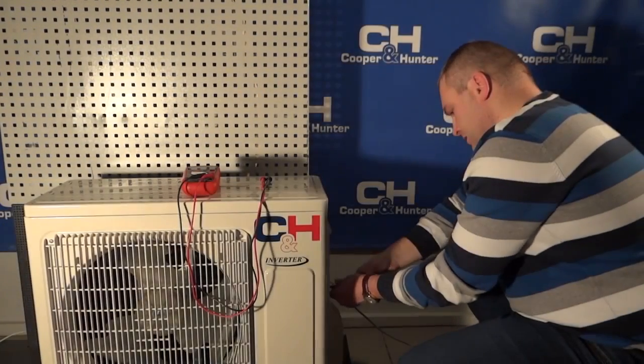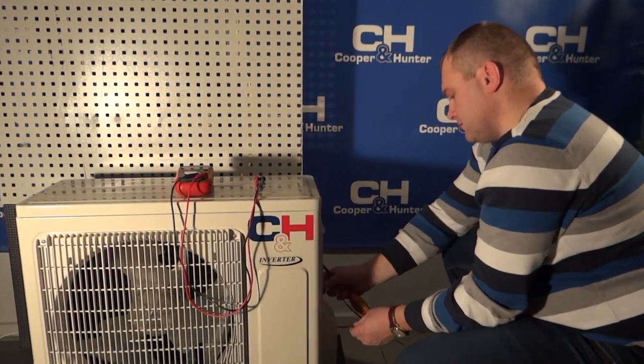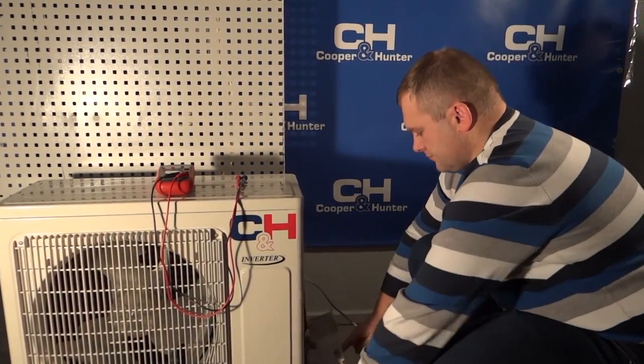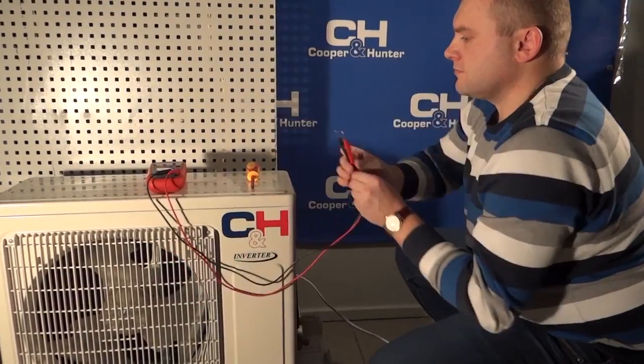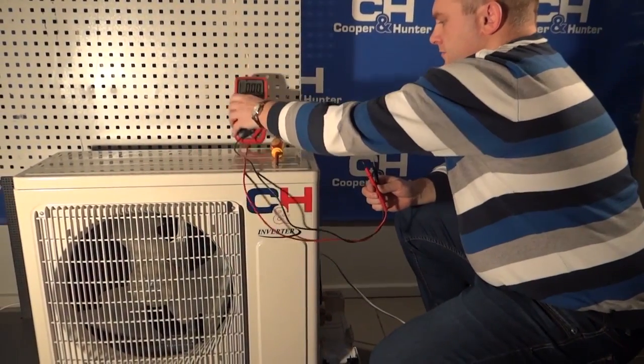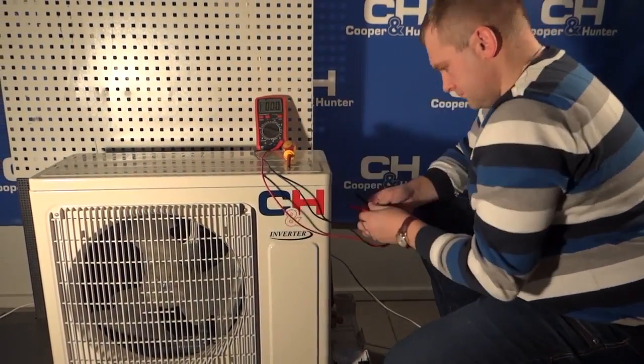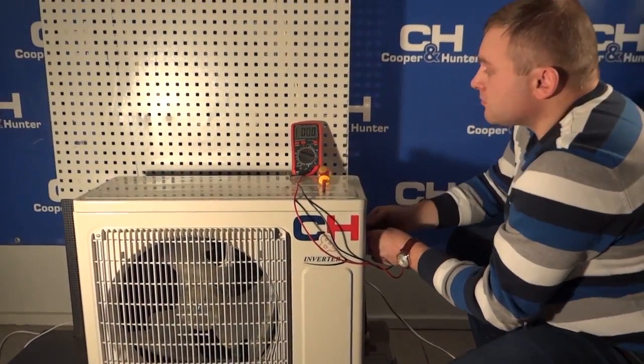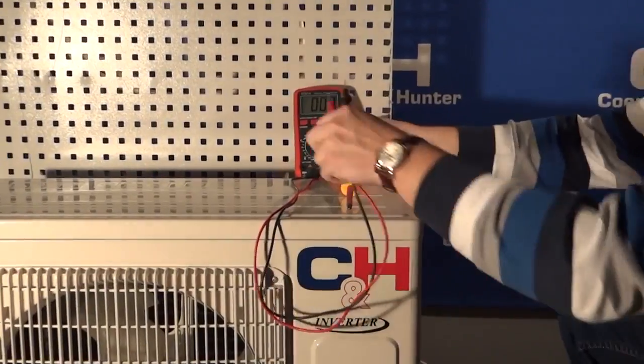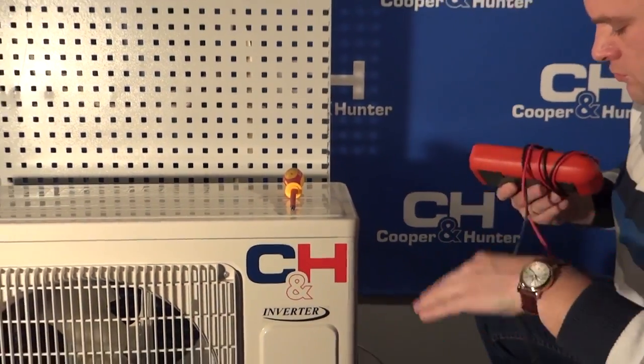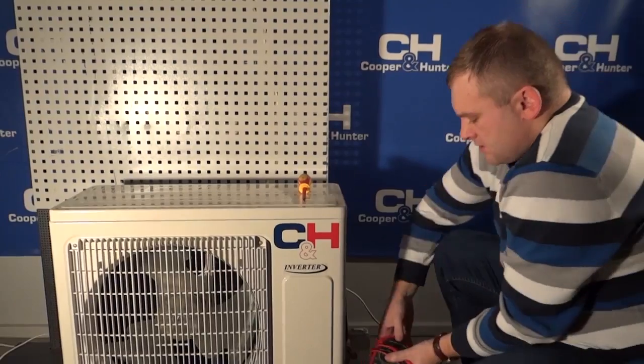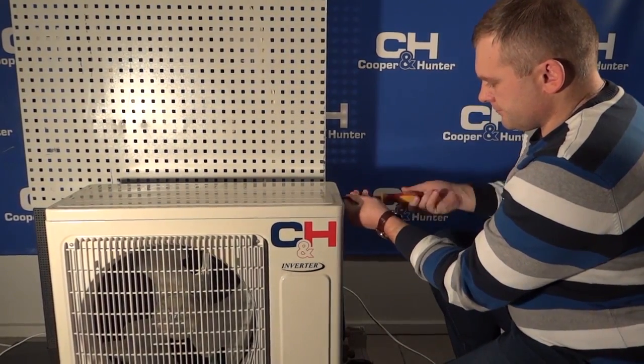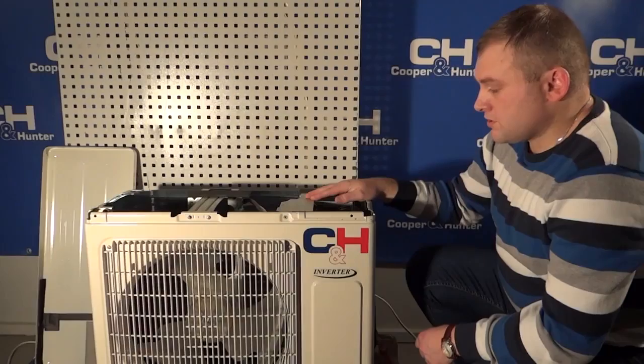We check whether there is power to the unit on the first and third terminals. Zero, no power. We remove the cover of the outdoor unit to access the main board of the outdoor unit.